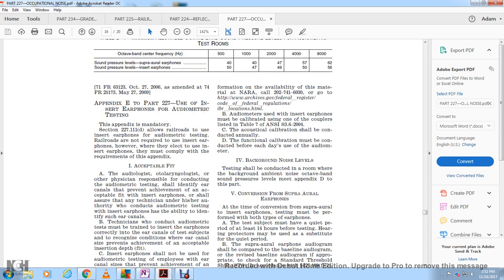Audiometers with insert earphones shall be calibrated using the couplers listed in Table 7 of ANSI S3.6-2004. Acoustic calibration should be conducted annually. Functional calibration must be conducted before each day of use. Requirement 4: Background noise level. Testing should be conducted in a room with background ambient noise octave-band sound pressure levels not exceeding those in Appendix D of this part.